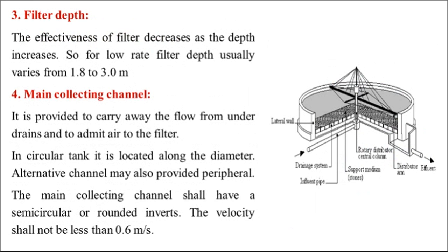Then next one, filter depth. In this figure, this is the filter depth. The effectiveness of filter decreases as the depth increases. For low rate filters, the depth usually varies from 1.8 to 3 meter.